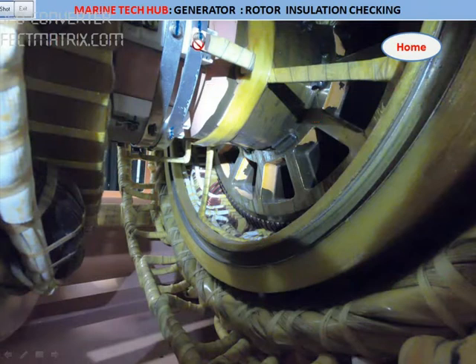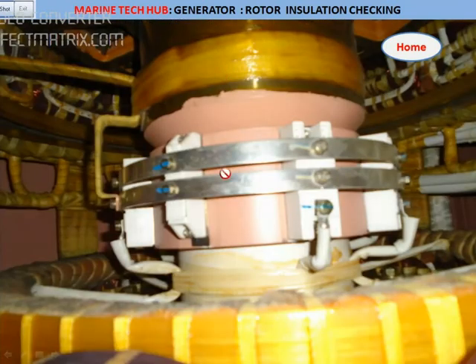You disconnect the terminal here — you can see one terminal coming here, one more here. So you disconnect it and put 500 volt DC; you will be able to get the insulation reading. But for the rotor side where the excitation takes place — the rotor side — for the field, you can remove the 24 volt connection and apply the megger to the rotor side.